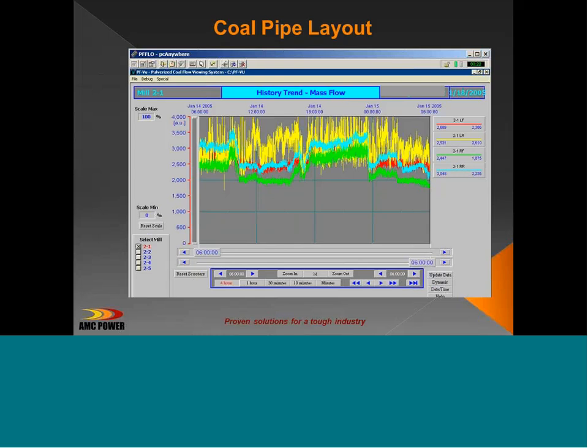This is another 4-coal pipe pulverizer. This time we're looking at the coal mass flow output from the air monitor SCADA system. So our data acquisition system here is showing a 24-hour window of data. And the blue pipe, the green pipe, and the red pipe are what we call normal operation. And the yellow pipe is erratic.